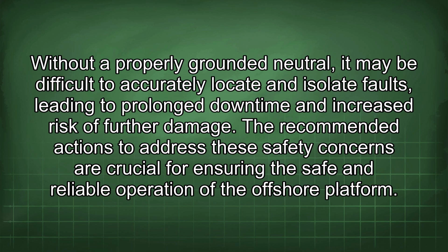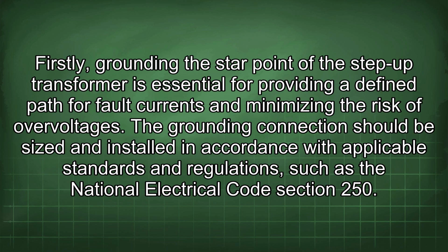The recommended actions to address these safety concerns are crucial for ensuring the safe and reliable operation of the offshore platform. Firstly, grounding the star point of the step-up transformer is essential for providing a defined path for fault currents and minimizing the risk of overvoltages. The grounding connection should be sized and installed in accordance with applicable standards and regulations such as the National Electrical Code Section 250.